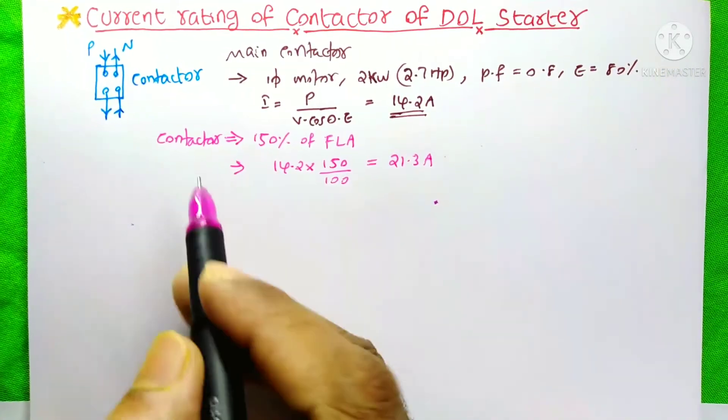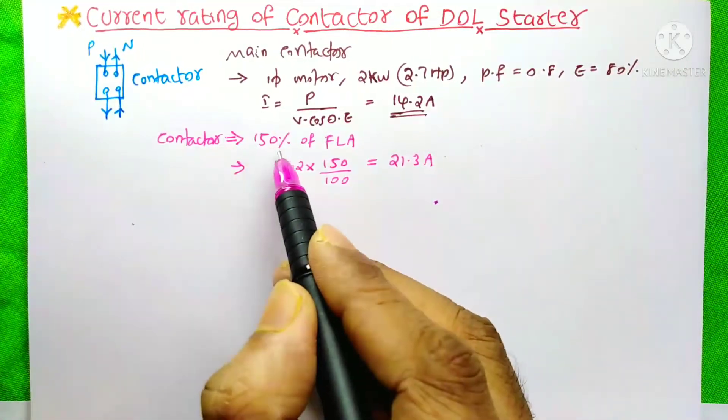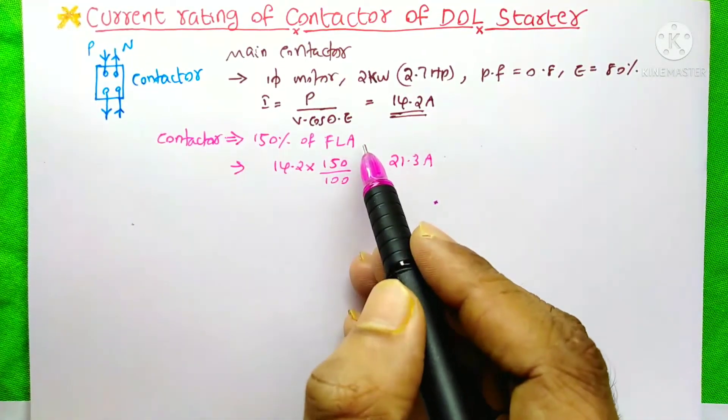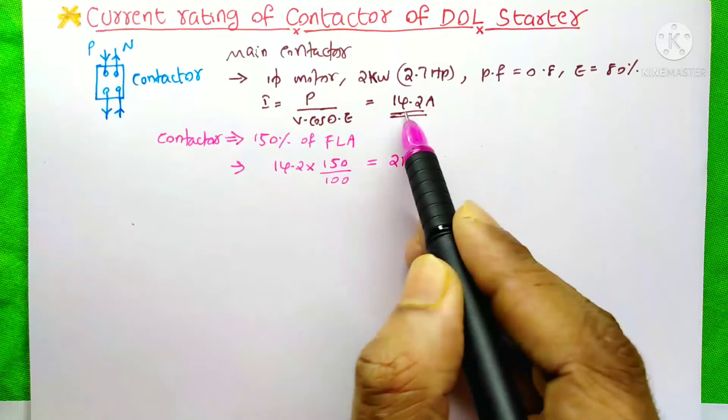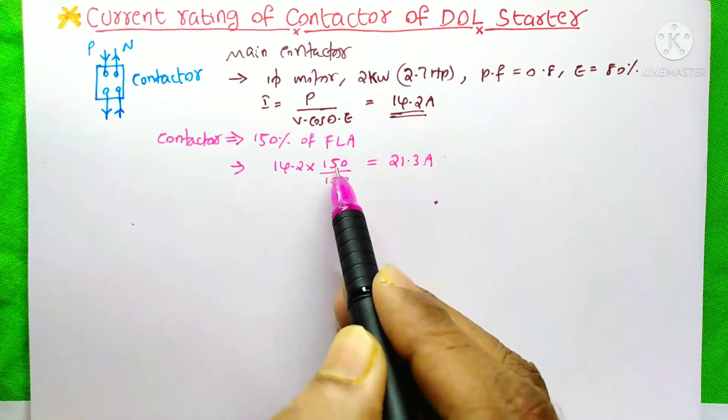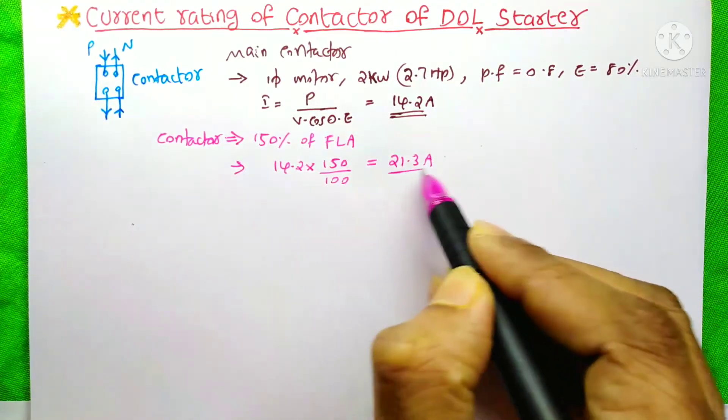You know in industry, the general standard is taking 150% of full load amps. That means our full load amps is this one. So 14.2 times 150%. The answer is 21.3A.